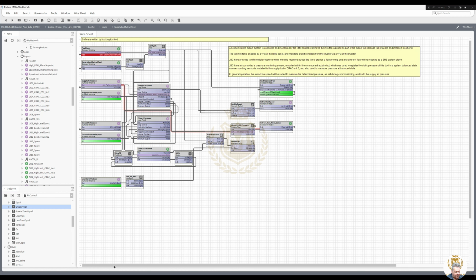Again, I haven't got a fresh air damper output, so I can't do anything with that. Call from the BMS system to open the damper and provide fresh air if the CO2 levels rise. So I'm monitoring the CO2 levels, and if they rise between these points, so above 800, switch off at 500, adjustable. But I don't have an output. These are all my outputs. Thyristors, the D-strap fan's done, Legionella done, general extract fan done, that's done. CRAC units, flow lamp, reception alarm, and that's my speed. They're all my outputs that I've got in the panel.